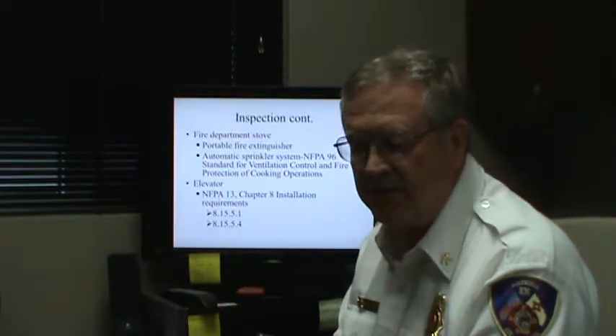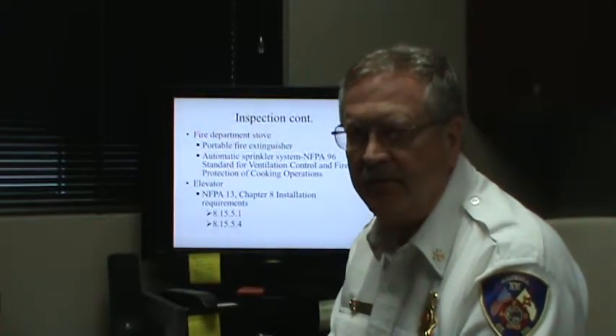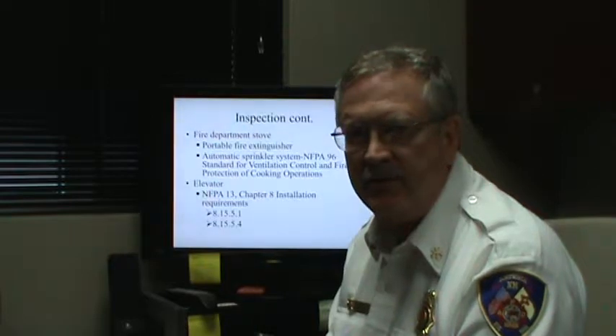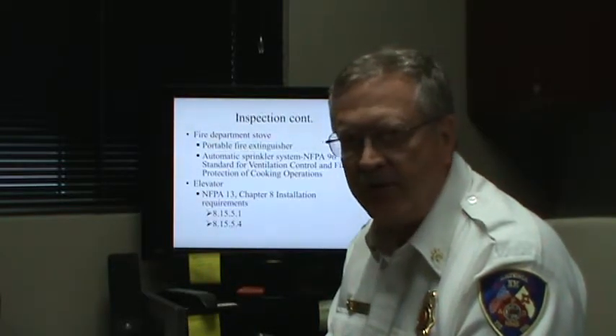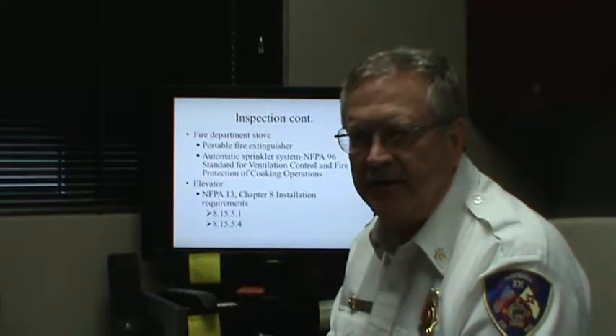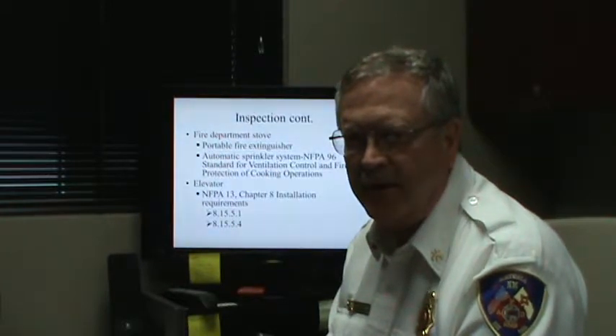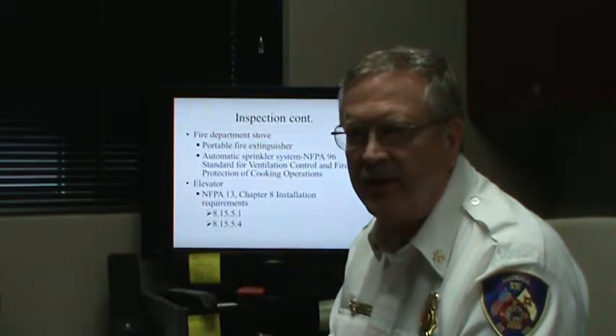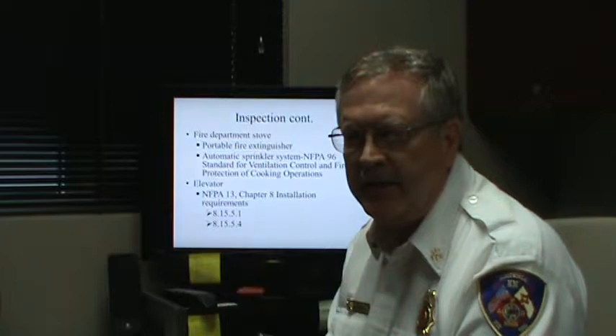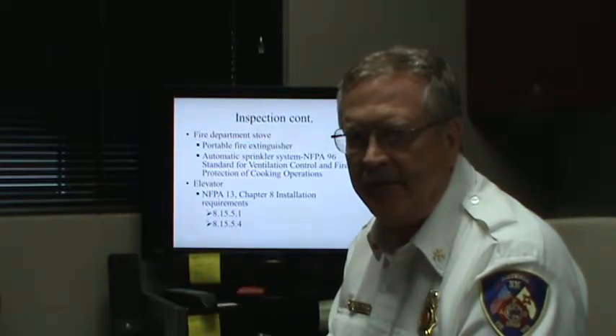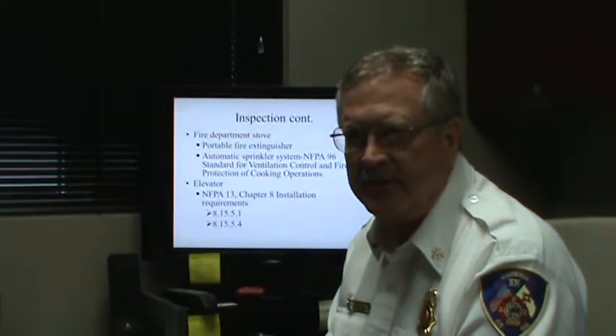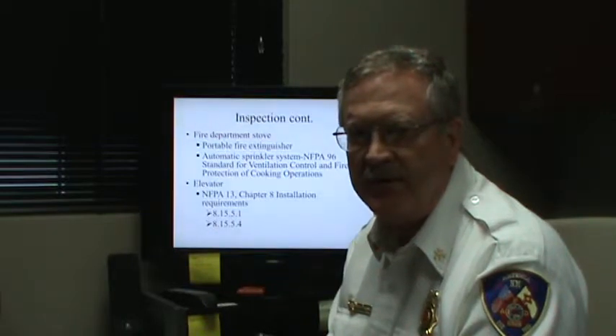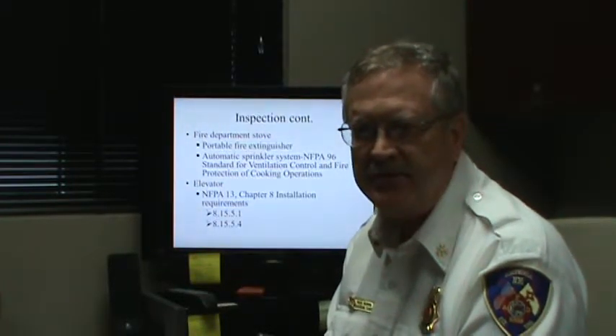96, because when they do cook some of their meals, it does produce a grease-laden vapor, and that's why we need to have that there. I did check the caps. The caps are covering the sprinkler heads. I did see the initial inspection or acceptance back in May of 2011 when we actually did the inspection acceptance of the sprinkler systems and the other fire suppression systems.